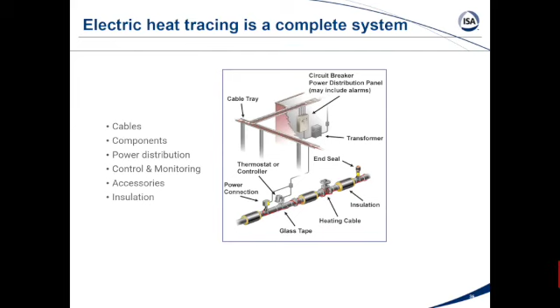So it's easy for us to see that, and we see it all the time, but people that are involved in it say, "No, this is our plant spec. Plant says 1 inch of this, and that's all we're going to get on there. And we don't care if there's more room for more, it's 1 inch." That's the kind of value when you really look at these systems as a whole, as opposed to saying, look at our insulation spec in this section, look at our heat tracing spec in this section, and just do what it says. When you really look at all these together as a system and not different puzzle pieces, you can really have a lot of savings. And on top of the savings, you have less cost of equipment, and then you'll have a more reliable system at the end of it, which is really what we're driving towards, educating the industry to really think of it this way.